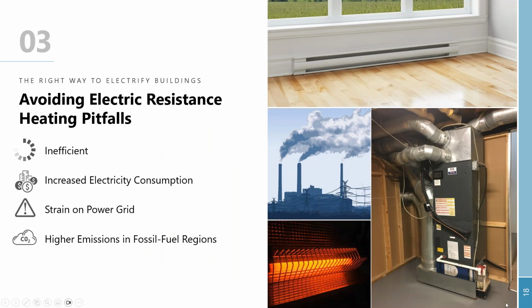Okay. There are better ways than others to electrify buildings. From a heating perspective, electric resistance heating may seem like an obvious choice to electrically heat a building, but it's much less efficient than heat pumps and should be avoided for building electrification. Electric resistance heaters include electric furnaces, baseboard heaters, electric unit heaters, etc. While they're electrically efficient in converting electricity directly to heat, they are thermally inefficient compared to heat pumps. Electric resistance heaters use more power to produce the same amount of heat versus heat pumps.